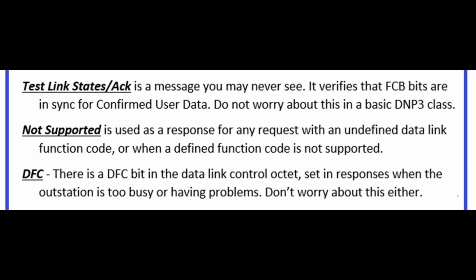The not supported function is used as a response for any request with an undefined data link function code, or when a defined function code is not supported. And there is a DFC bit in the data link control octet set in outstation responses when the outstation is too busy or having problems. I have never seen this used. Don't worry about it either.